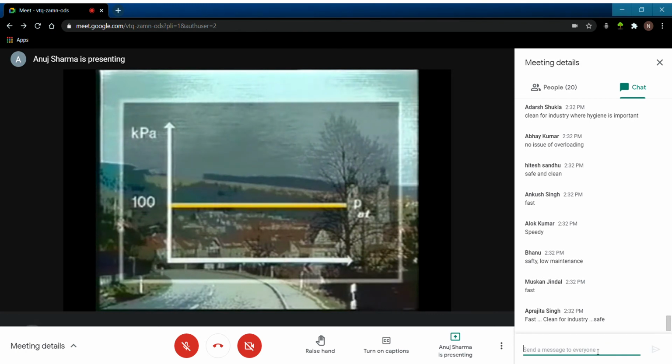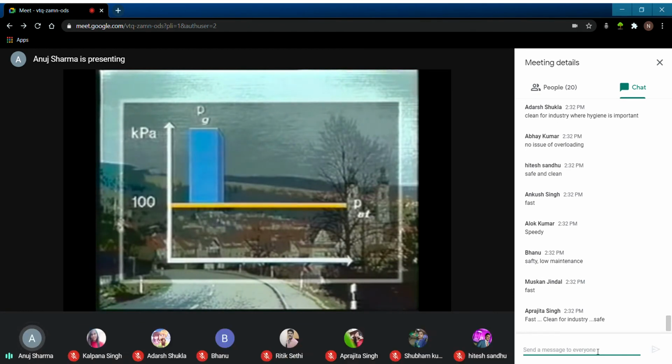All pressure measurements taken using atmospheric pressure as the 0 point are designated gauge pressure, or P sub G. Pressure gauges attached to pneumatic circuits usually indicate pressure as gauge pressure. From this point on, whenever P is used without a subscript, it is indicated in gauge pressure. Absolute zero pressure is 100 kilopascals below gauge pressure. Any pressure below gauge pressure is called vacuum, or P sub V. Therefore, absolute pressure is the sum of vacuum and gauge pressure.